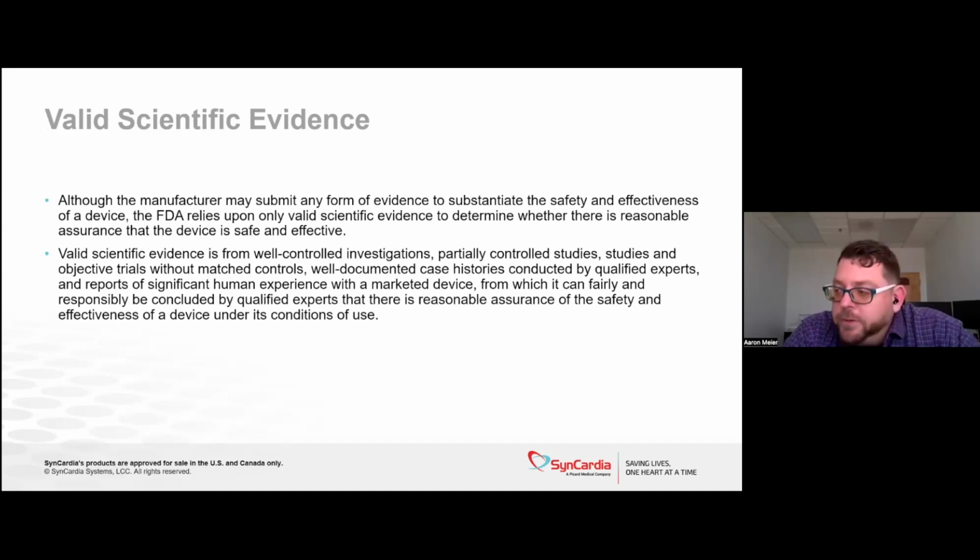When you make your submission to the FDA, you can use any data sources you want to demonstrate the safety and effectiveness. The FDA then can decide whether or not the evidence you provided is considered valid scientific evidence for the determination of the safe and effective use of your device. So you can provide them studies with sample sizes of 2, journal articles from Google, and some testimony from your cousin, and it might make the device look really good. The FDA does not have to accept that.